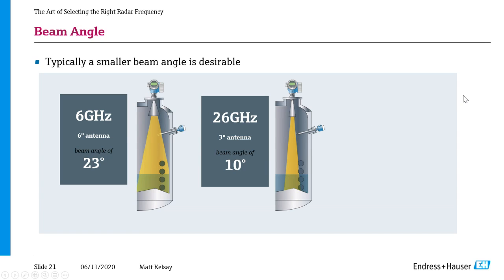If you go to the next and look at what a 26 gigahertz radar might look like in this application, here we can shrink it down to a 3-inch antenna. So we cut that size in half, means your tank opening is much smaller, and we drastically reduce that beam angle. So now maybe we don't have any influence or signal return from the tuning fork or the switch up in the top of the tank, but as that signal spreads out as it goes down into the bottom of the tank, maybe you do still get a little reflection off of your heating coils or baffle plates. So again, a good mapping of the tank is still probably needed here.